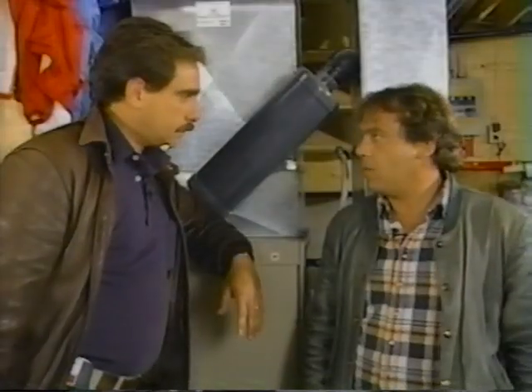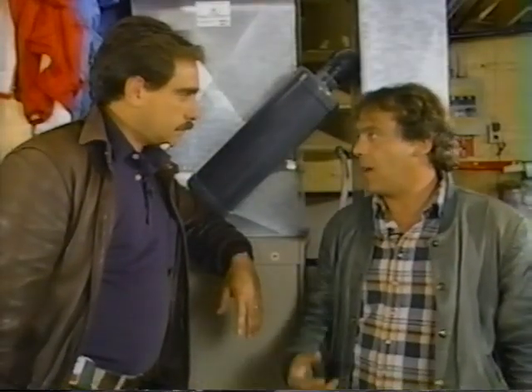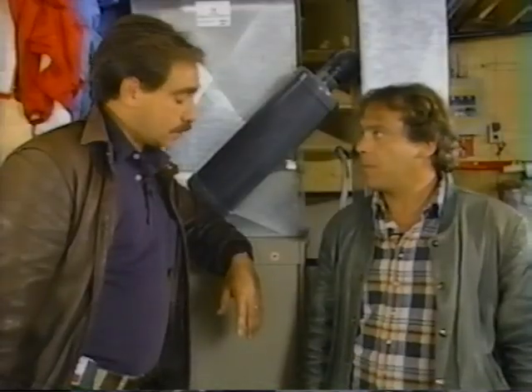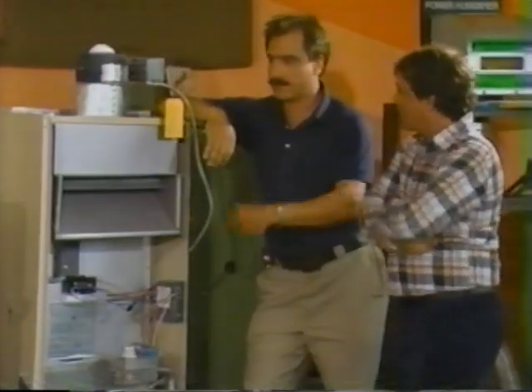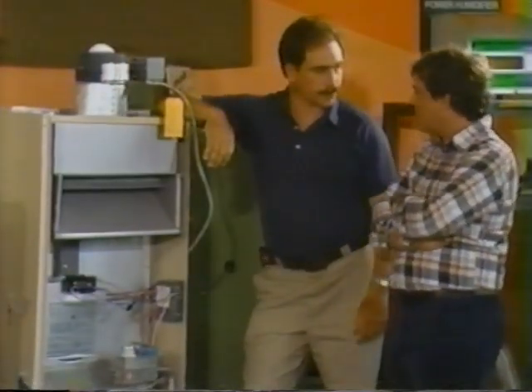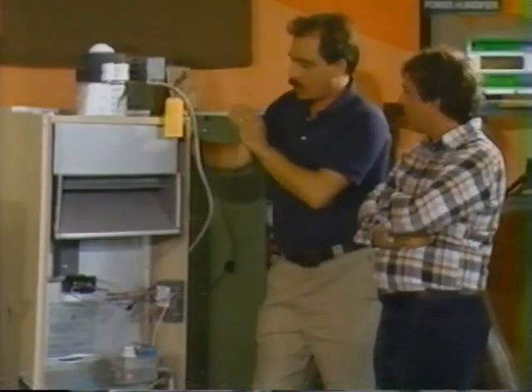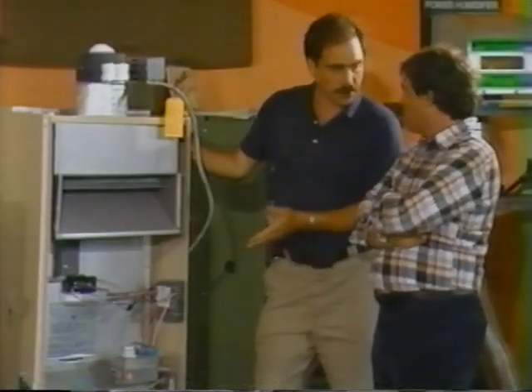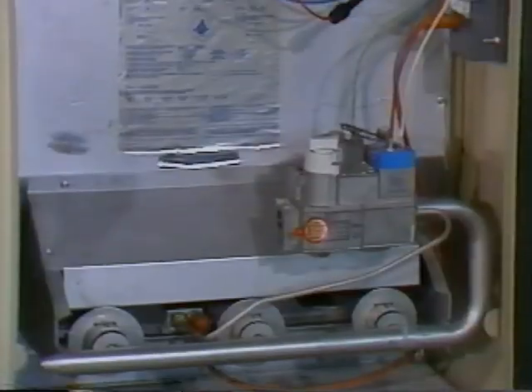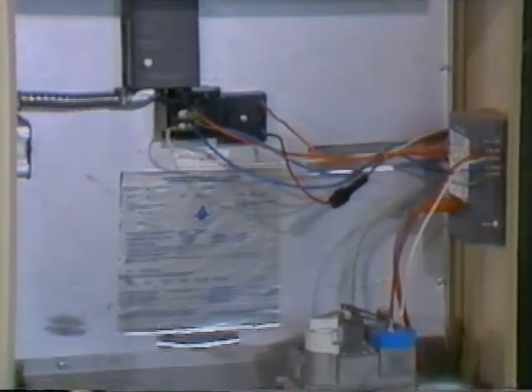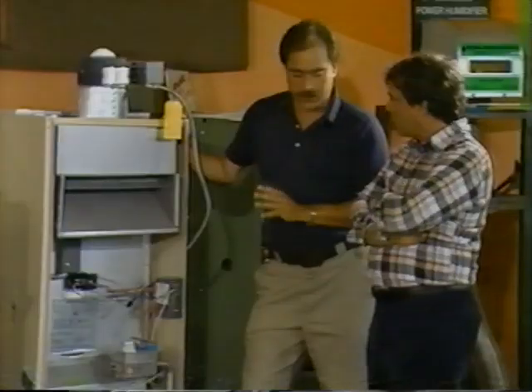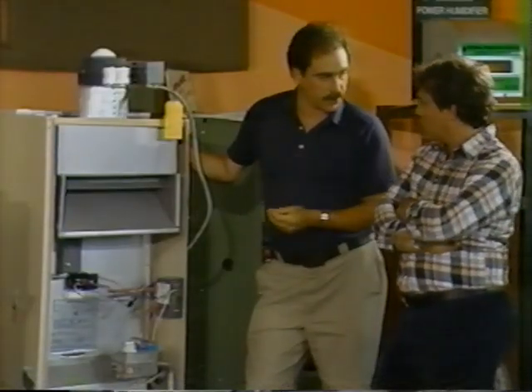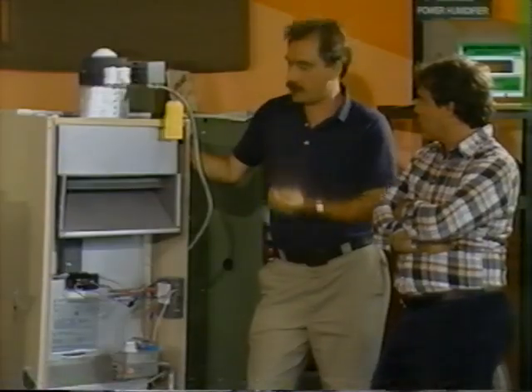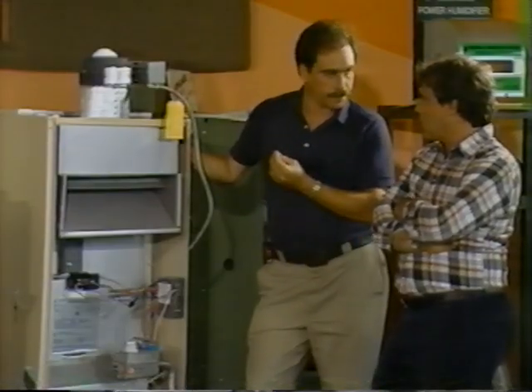Well, I'm ready to go back to that store and look at some of those different high-tech furnaces because I'm not too up on them. Let's go. Well, David, we've got a whole bunch of furnaces to go through, so let's knock them down. What we're looking at here is a conventionally aspirating furnace. It has electronic ignition and a flue damper, but other than that is completely conventional. It is verboten in an energy-conserving house. The reason for that is that it relies on waste heat to create the draft in order to exhaust the flue gases. In other words, the stack effect.